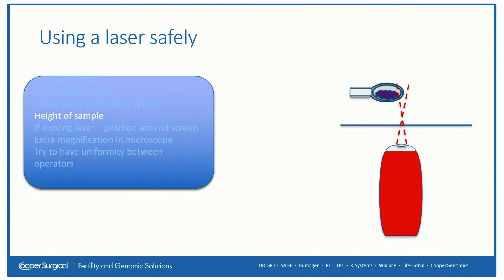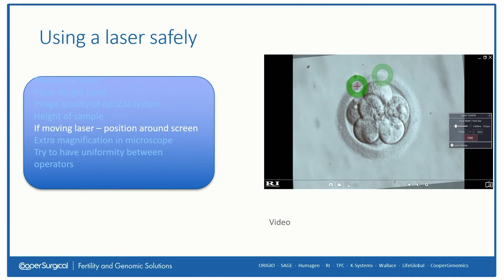Now, if you have an active or dynamic laser, it is a good idea to periodically check that you get the same results, in our case, we're talking about a hole, at all places where the laser can move to. So I just do a couple of clicks with a sample embryo around the screen, making sure we get the same results.